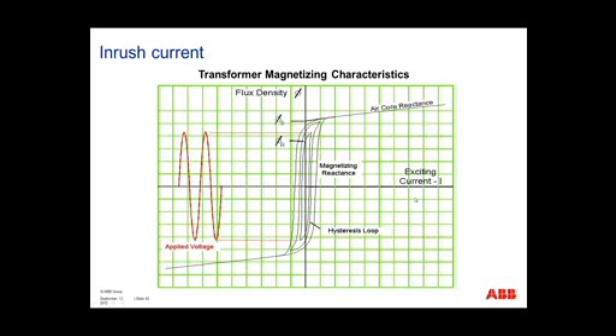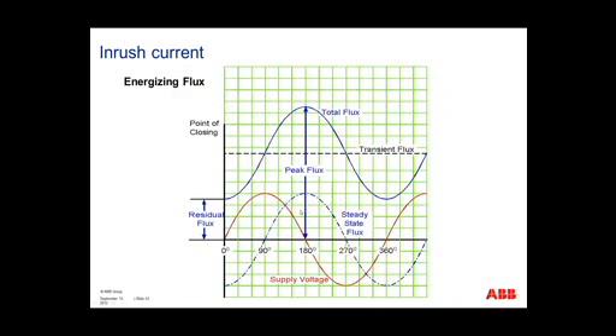So on this BH curve, trying to represent the inrush and the remanence inside the core, the inrush is directly proportional to the voltage applied to the transformer. And here we can see on this BH curve the inrush current going through the flux of the core and its rotation. We can also see the total flux, and this of course is the worst case if we have a closing of the breaker feeding the transformer at the 0 crossing of the voltage. You can see the total flux will be at its peak after the half cycle of voltage. This would be the worst case scenario, and this is what you need to account for to block your differential protection from operating.